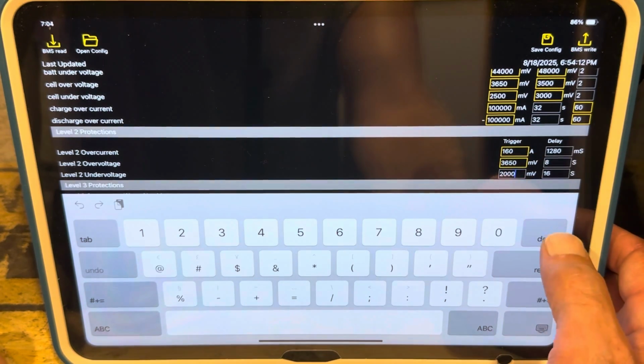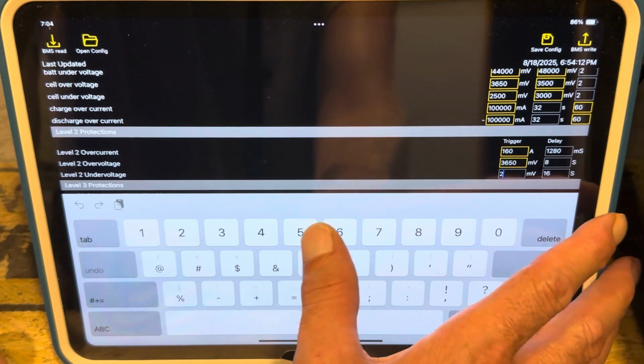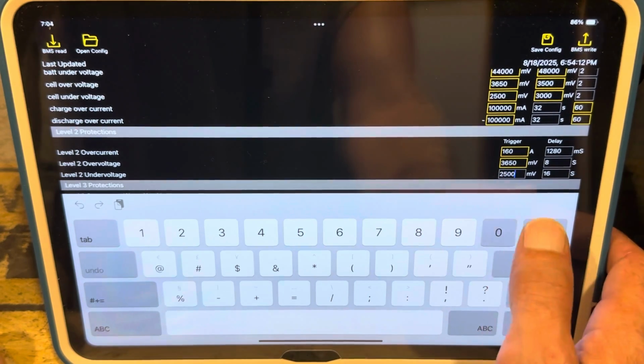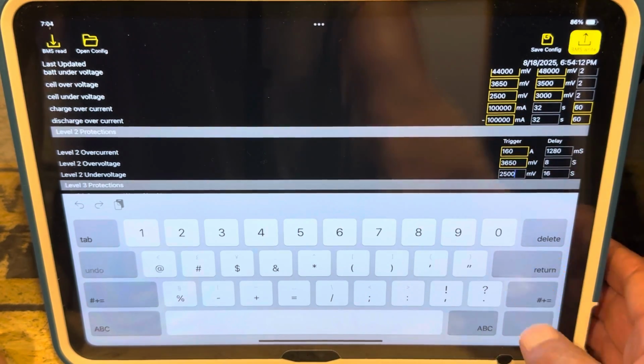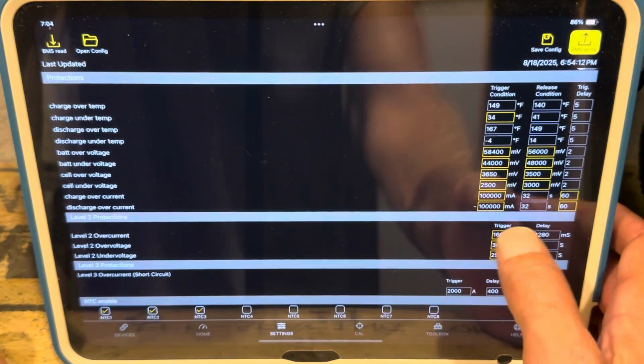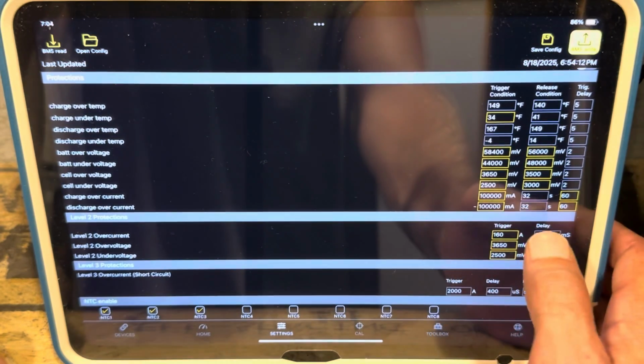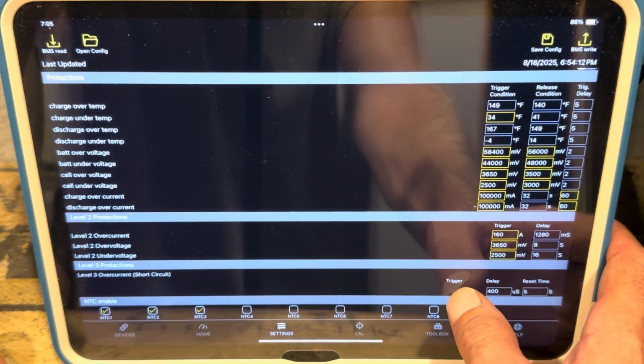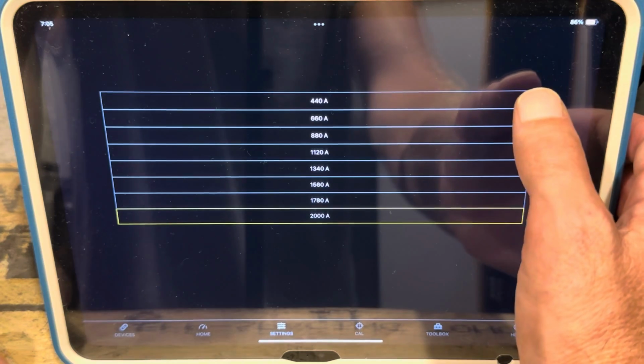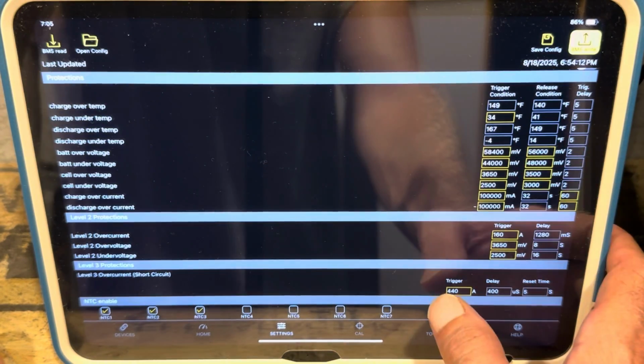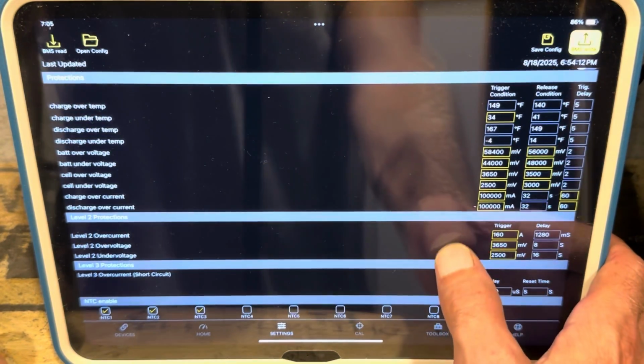The level 2 under voltage, I'll just put that at 2.5 volts per cell as well. Leave the programming in right there because this will catch it well before that does. So leave that there. And then the short circuit protection, 2,000 amps, that's way up there. We're going to bump that back down to 440 amps. That should be a lot more conservative. So that's good right there.